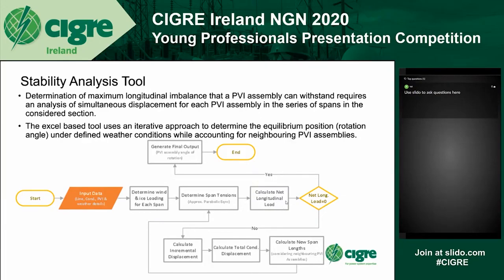Then it calculates the net longitudinal load for each PVI assembly. In instances where a net longitudinal imbalance exists, the conductor attachment point for the PVI assembly is displaced by an incremental displacement value calculated by the tool itself.